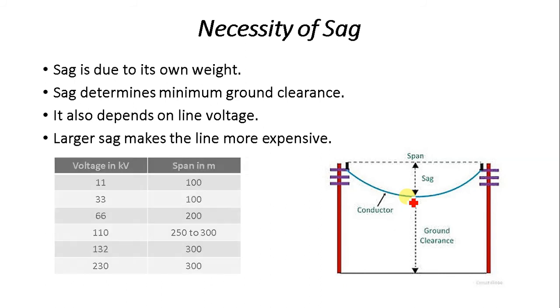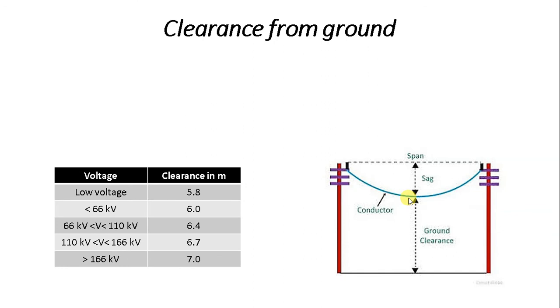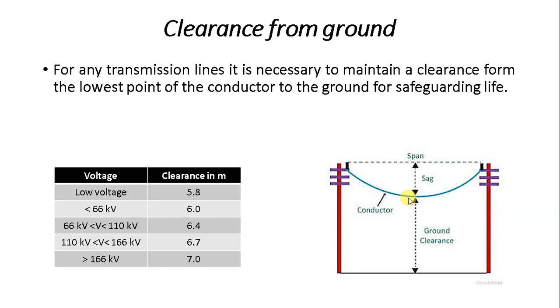The table shown here is about span values. Sag also depends upon the value of span — if the span is less, the sag is small. For ground clearance, it is necessary to maintain a minimum clearance from the lowest point of the conductor to the ground to safeguard life — whether human beings or animals. The clearance depends upon the voltage level of the transmission line. As shown in the table, for low voltage it is 5.8 meters and for greater than 166 kV it is 7 meters — these are minimum values.